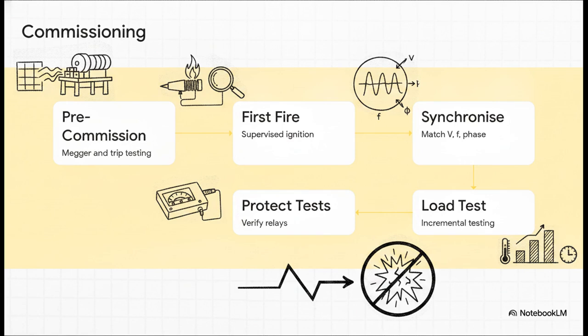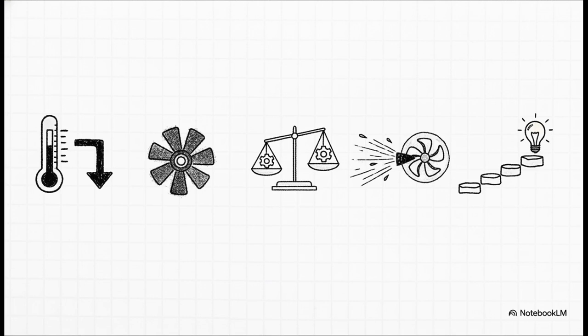And of course, when you're initially bringing the system to life, you've got to rigorously march through this exact 5-step sequence to ensure absolute safety and grid stability. First, pre-commissioning checks like Megger testing insulation. Second, the first fire, which is a highly supervised ignition. Step 3 is synchronization, where you perfectly match voltage, frequency, and phase angle to the bus. Step 4 is incremental load testing. And finally, Step 5 validates your under-frequency and over-temperature protection relays. Skip even one of these steps, and you are risking a catastrophic plant failure. Just don't do it.